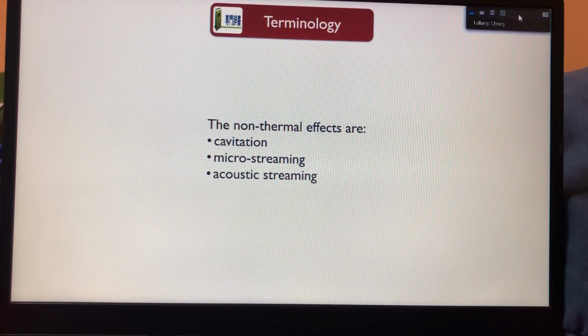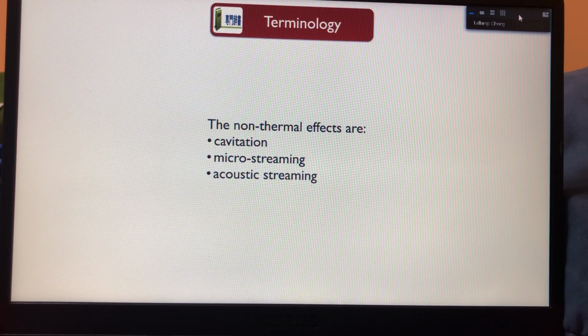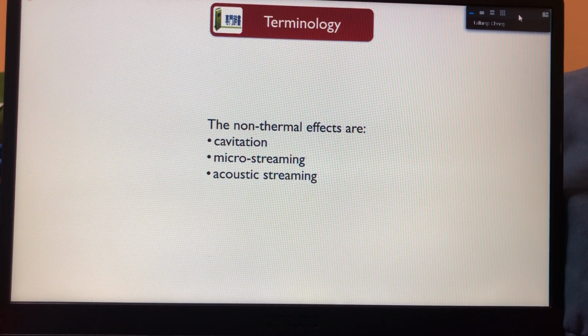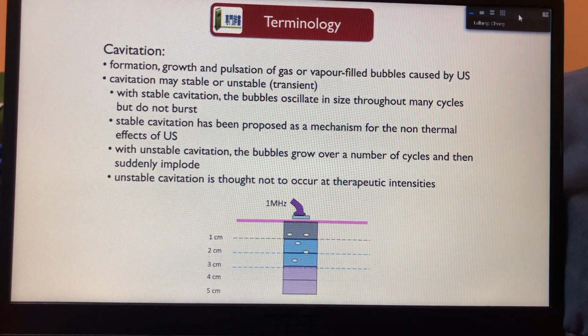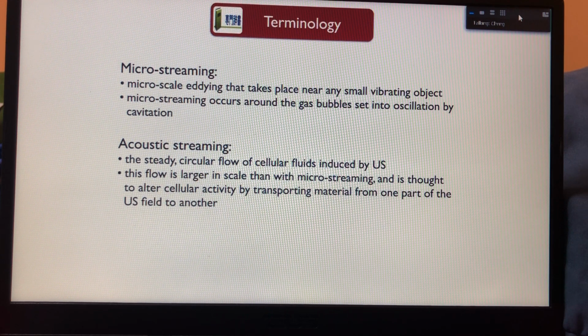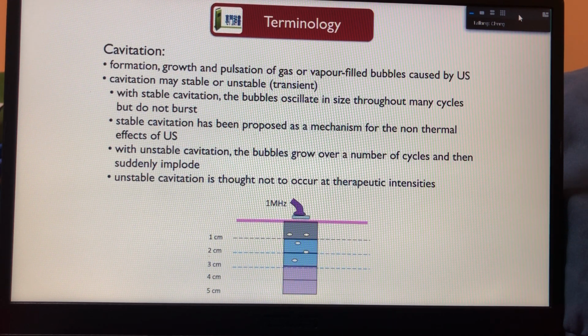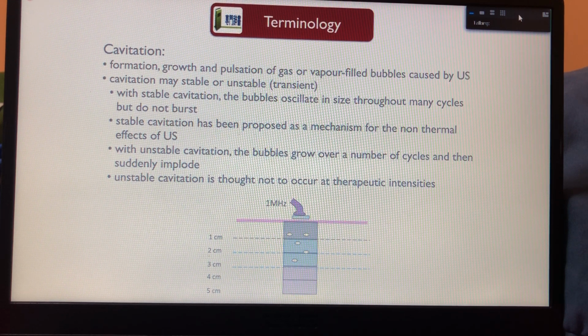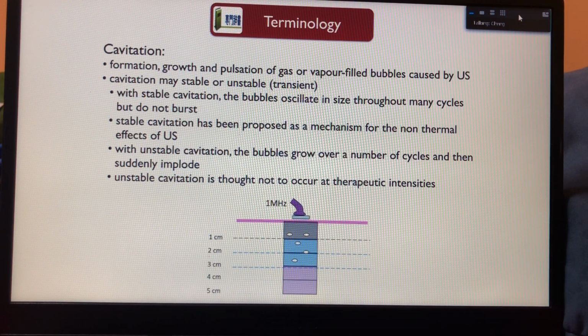Non-thermal effects just means that apart from the heating effect of ultrasound, which is caused by the molecules rubbing against each other, there's also cavitation, microstreaming, and acoustic streaming. Now, what's cavitation? Cavitation are the bubbles that occur in the field. What's microstreaming? Well, the bubbles that occur vibrate. And when they vibrate, the fluid around the bubbles will circle around it. What's acoustic streaming? Acoustic streaming is the summation of all that.